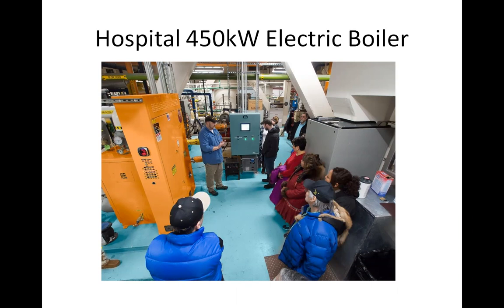So the electric boiler is plumbed into the return line to the oil-fired boilers, essentially preheating them. There's no controls interaction between the electric boiler and the oil-fired boilers — the oil-fired boiler controls just see hot glycol coming back to them so that they don't turn on.